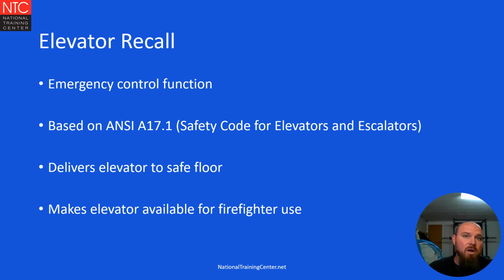The basis of recall and the elevator information is going to be coming from ANSI A17.1, which is the safety code for elevators and escalators. What recall does is it delivers the elevator to a safe floor, which then makes the elevator available for the firefighters and fire department use to put out the fire.